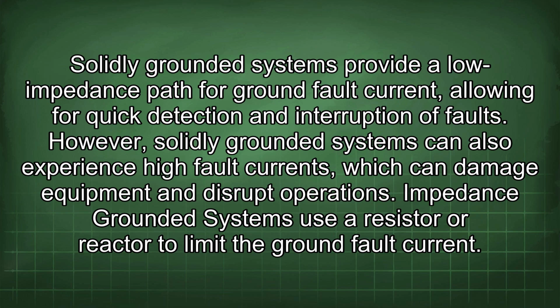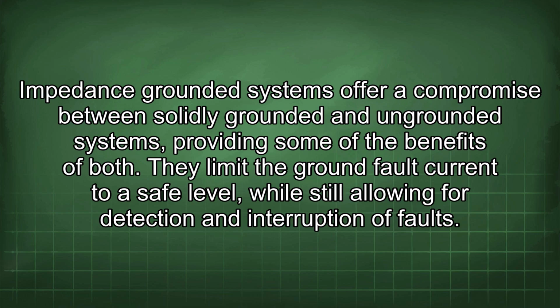Impedance grounded systems use a resistor or reactor to limit the ground fault current. Impedance grounded systems offer a compromise between solidly grounded and ungrounded systems, providing some of the benefits of both. They limit the ground fault current to a safe level, while still allowing for detection and interruption of faults.